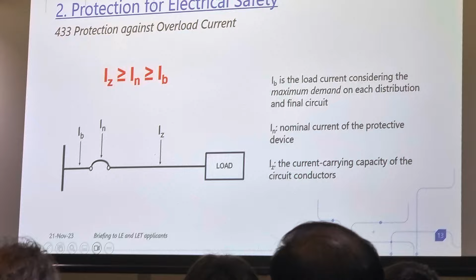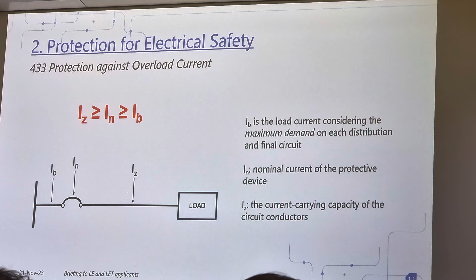So this formula, I think most of you are familiar with. But don't worry, we won't ask you to do calculation. This is not a session for an examiner. We would want you to understand the principle behind the formula. What's the principle behind the formula? There are letters we use, IB, IN, IZ. IB is basically the design current. We know there is a maximum demand, that means under the maximum load condition, this is the current that will flow. So in order to make sure that there is protection against overcurrent, our protective device must be higher than that. That's why IN, which is the rating of the protective device, must be higher than your maximum current. Now, if the cable needs to be protected, then IZ, which is the current capacity of the cable, must also be higher than IN.